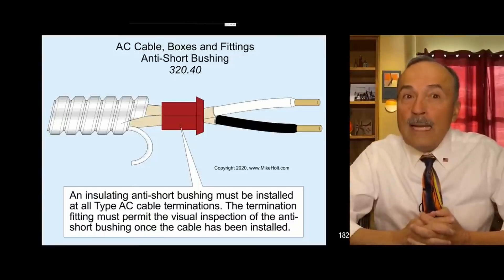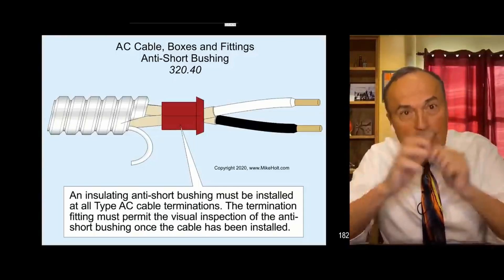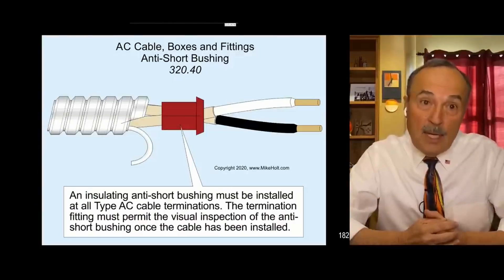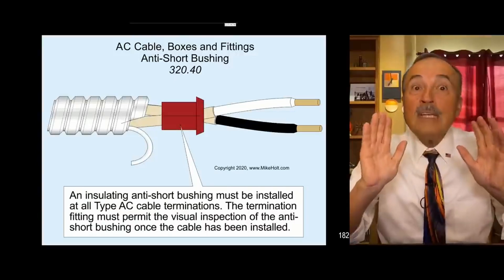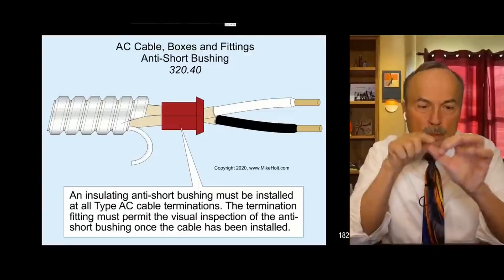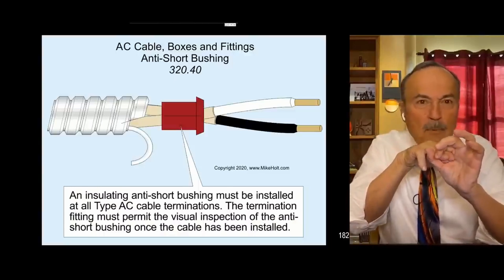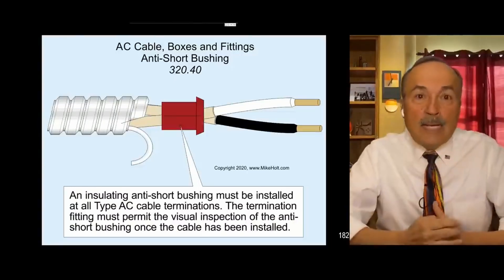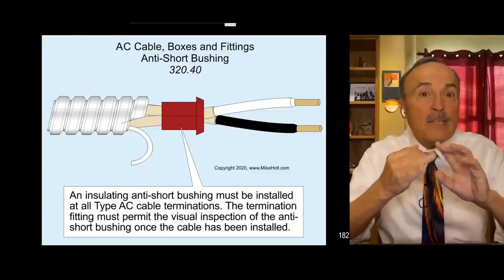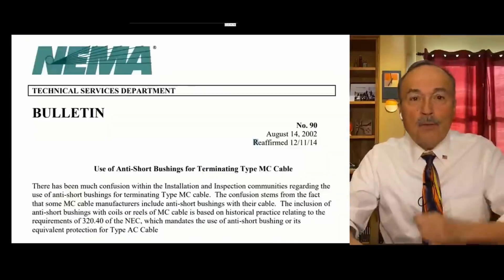MC cable requires a totally different fitting and does not require any visualization to see if the anti-short bushing is there. If you look inside an MC cable fitting, there's a stopper - a little ring stopper - and the conductors go within the ring stopper. Therefore there is no requirement for an anti-short bushing for MC cable because it is a different fitting and a different type of construction. So the answer is no.